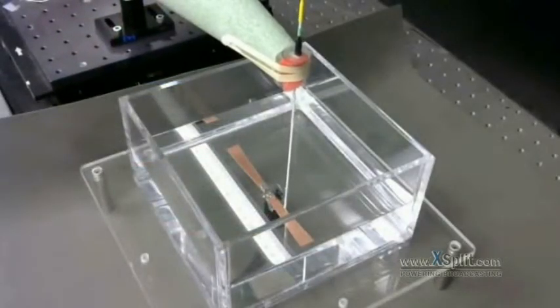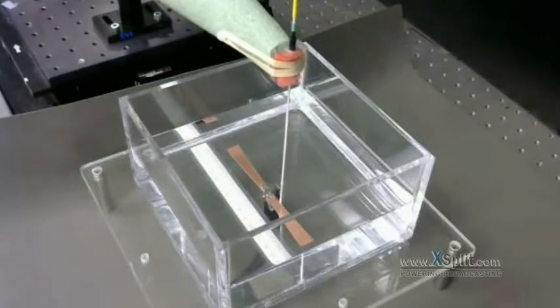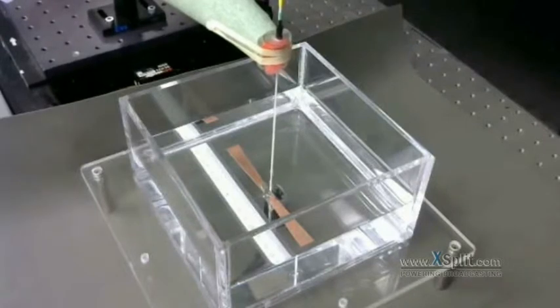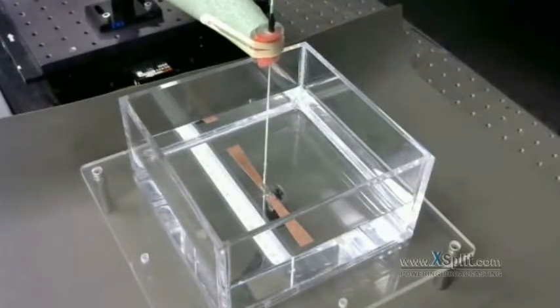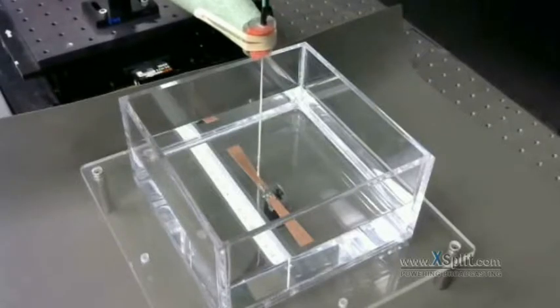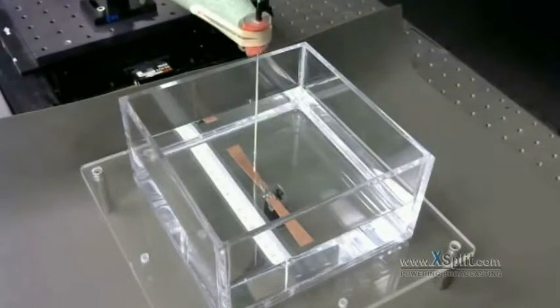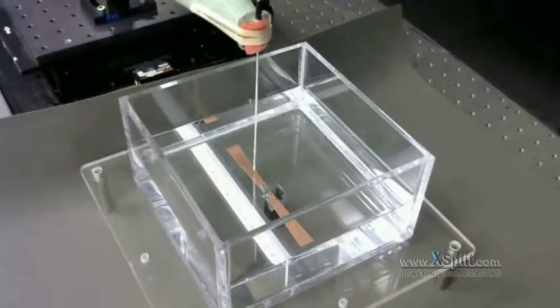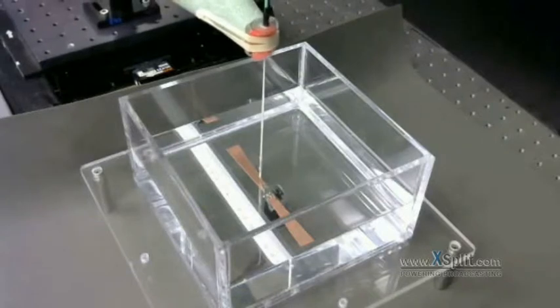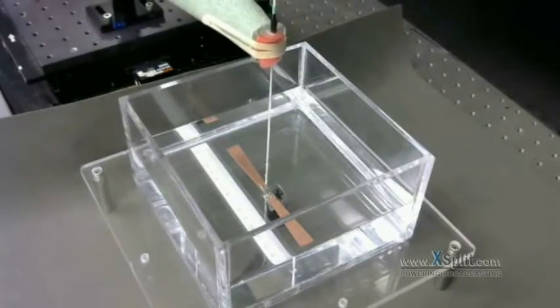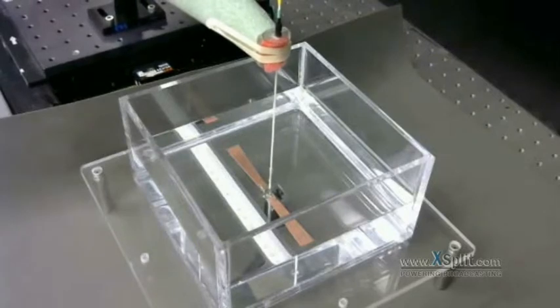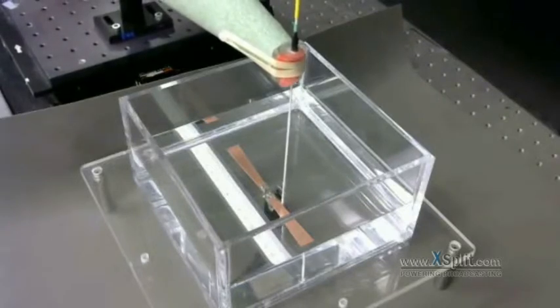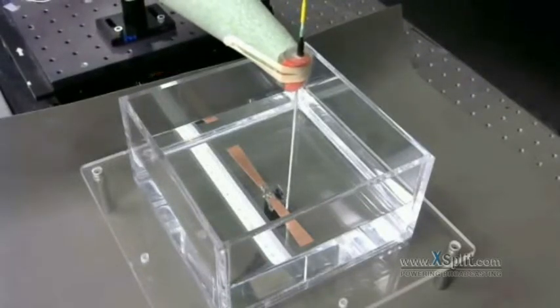In this window, we can more clearly see the dipole antenna device under test, or DUT, the water reservoir, and the glass stalk that structurally supports the electric field probe as it is raster scanned over a planar region above and parallel to the plane of the dipole. The antenna itself is comprised of two copper film segments separated by a gap and fed through a coaxial cable from underneath its plexiglass substrate. The plastic box that serves as the water reservoir sits just on top of the dipole. The electric field probe employed here is known as a tangential electro-optic probe because it is sensitive to the field that is parallel to the plane of the DUT.